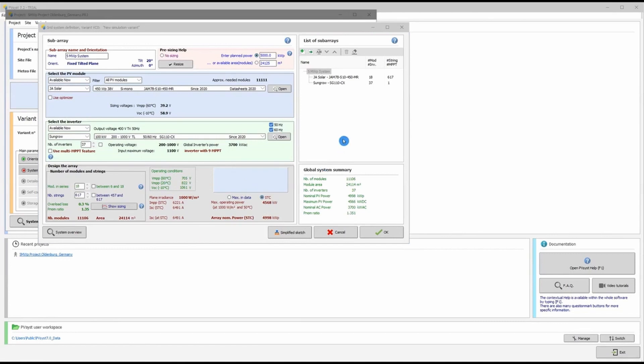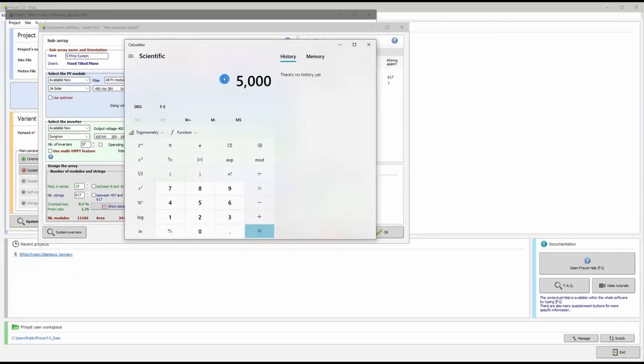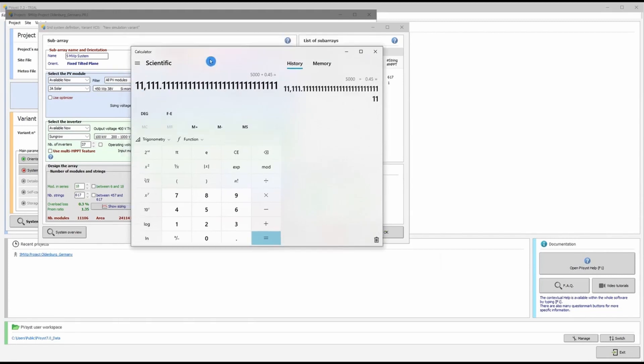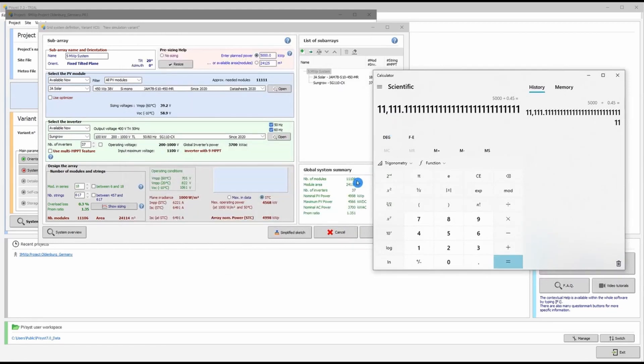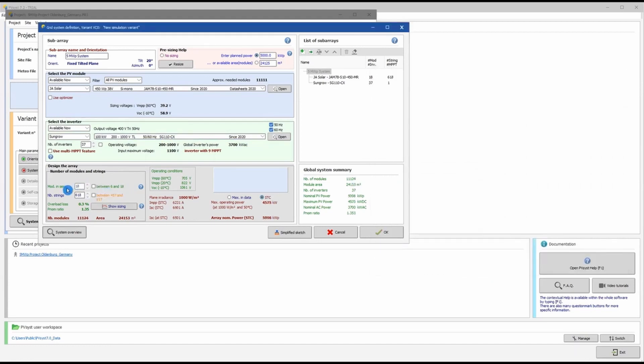In the global system summary, PVsyst shows that the defined system is 4.998 MW instead of 5 MW. To achieve exactly 5 MW: 5000 kW divided by 0.45 kW per module gives approximately 11,100 modules — about 5 panels more than configured. By adding one extra string of 18 panels, we go slightly above 5 MW.